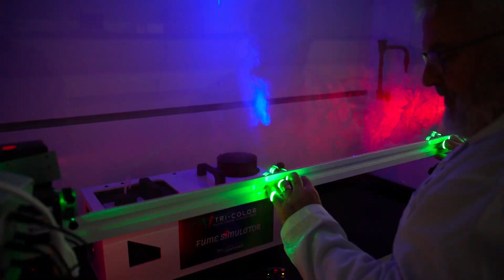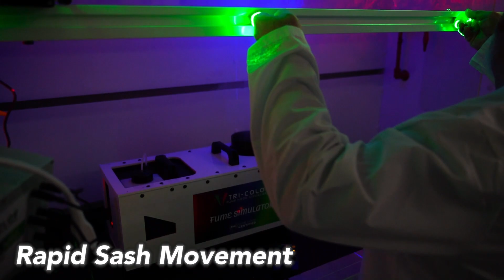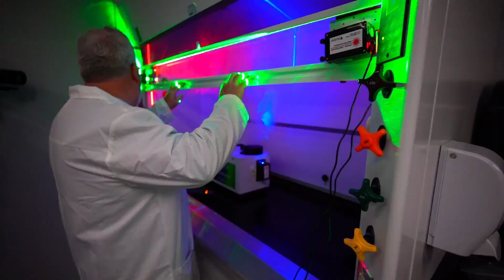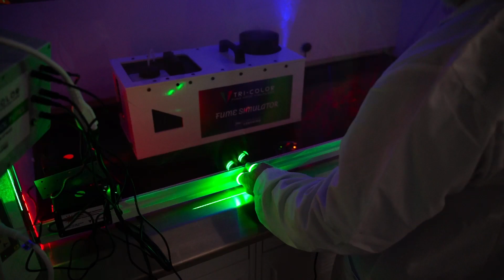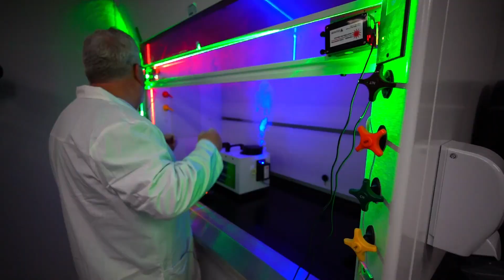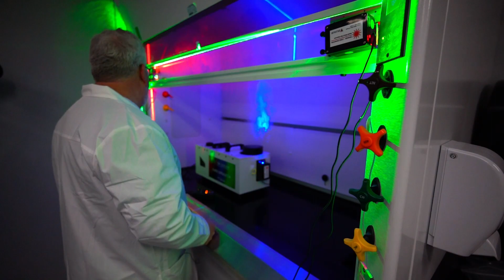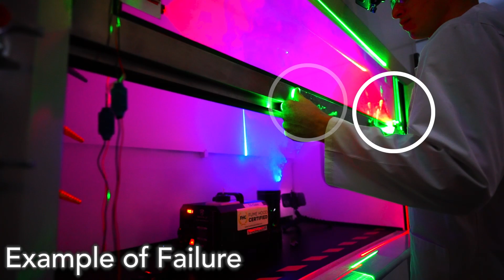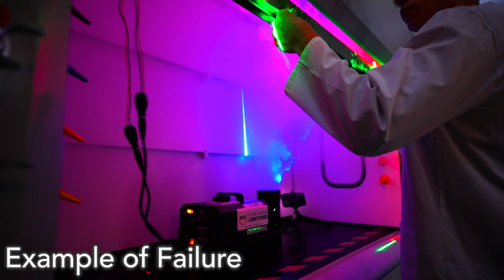On a failing hood, you can see a somewhat sheet of lazy smoke definitely coming out and into the breathing zone. Opening and closing the sash can cause loss of containment, especially at the edges of the sash. So we do a rapid sash movement challenge to see if movement from the sash will pull air out of the hood and light it up in green for us to see it. Observe what the red smoke behind the sash is doing and watch for any green loss of containment. On a failing hood, notice how we can see the loss of containment when the sash moves up and then stops. It's kind of lazy, it's kind of small, but it is still chemicals that are exiting the hood into the breathing zone, and we want to prevent that.